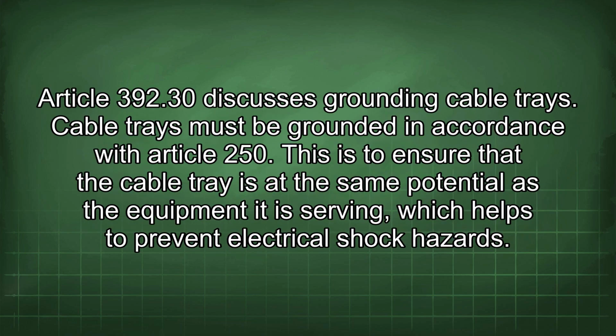Article 392.30 discusses grounding cable trays. Cable trays must be grounded in accordance with Article 250. This is to ensure that the cable tray is at the same potential as the equipment it is serving, which helps to prevent electrical shock hazards.